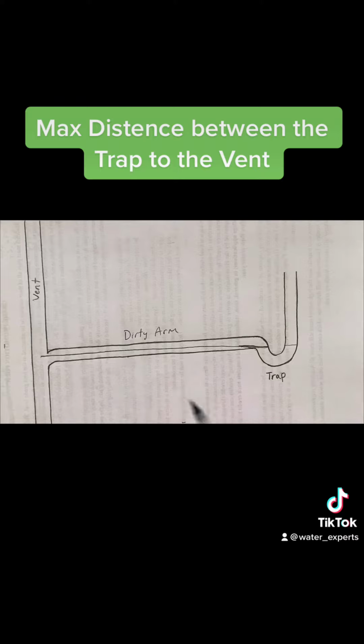So we're going to talk about the minimum and maximum distance. Now, a good way to remember is you're going to times the size of the dirty arm. You're going to times that by 4. So if it's a 1.25 inch pipe, we're looking at 5 feet. If it is 1.5 inches, it's 6 feet, and so on.